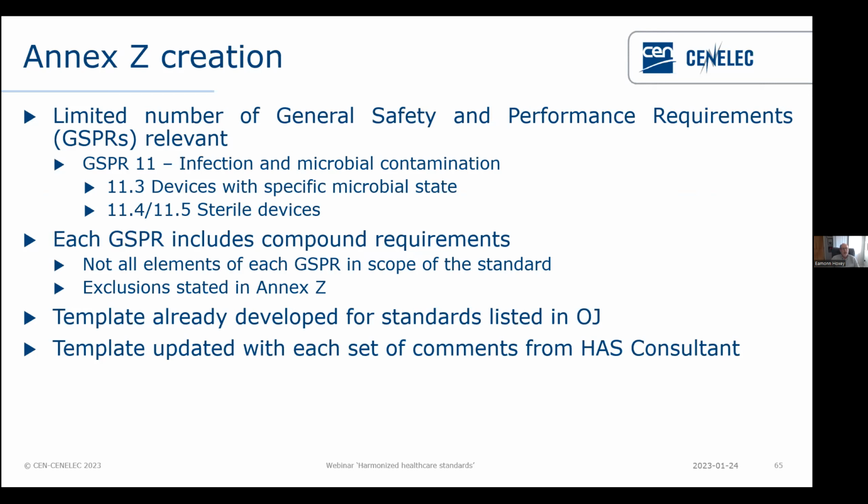And one of the things that we had to bear in mind was that each of those GSPRs that we were dealing with has a number of requirements contained within a single GSPR. So they were compound requirements, and not all of those bits of the GSPR were within the scope of the standard. So we had to be very specific in the Annex Z as to which parts of the GSPRs were covered and which parts of the GSPRs were not covered.